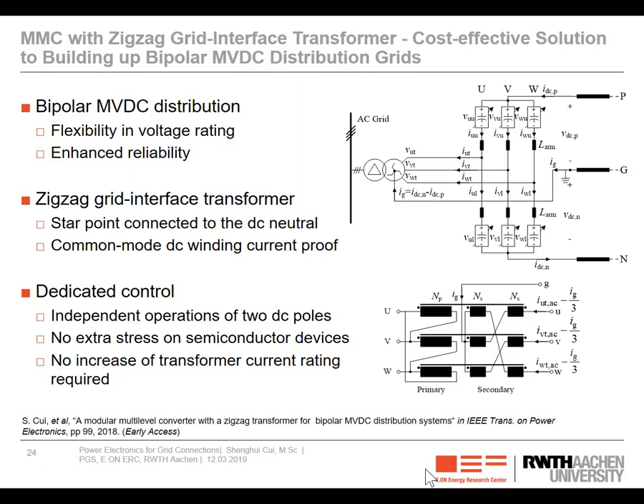And the nice thing of this configuration is that compared to the conventional configuration for unipolar medium voltage DC distribution, there's no penalty of increased stress on both the semiconductor devices and the transformer. So we can enable fully bipolar operation capability almost without any penalty of extra cost.